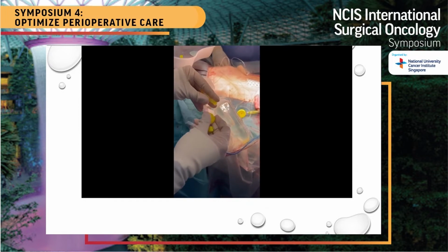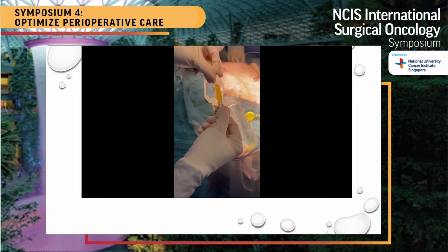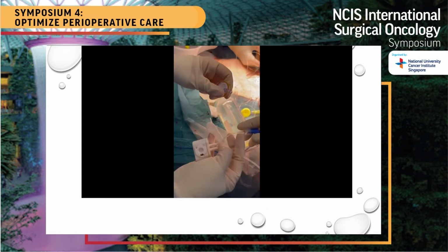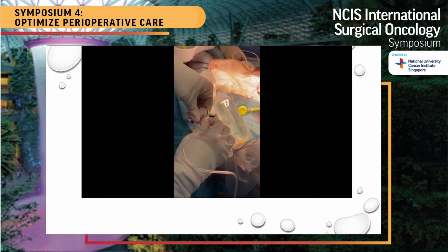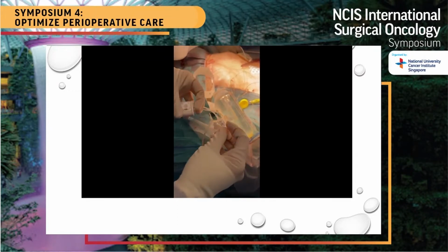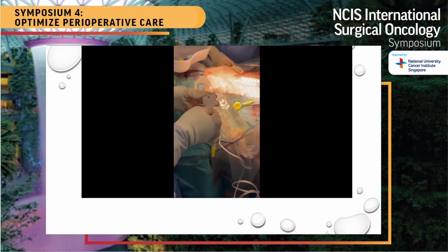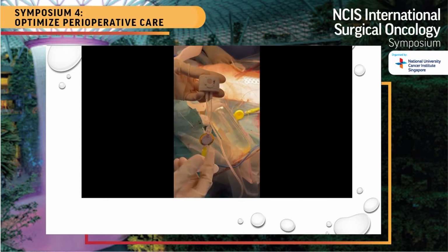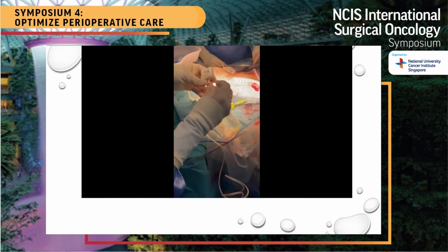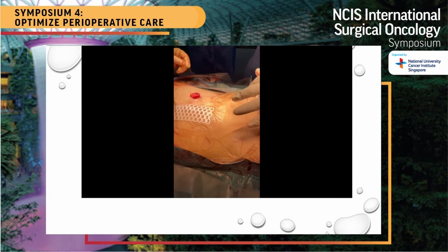Subsequently, the filter is connected and then the elastomeric pump connected. The rate is adjusted using the provided key to 7 mL per hour. And to indicate that the pump is working, sometimes you can see a bubble running through the tubing. The reservoir also will shrink with time to show that it is working.